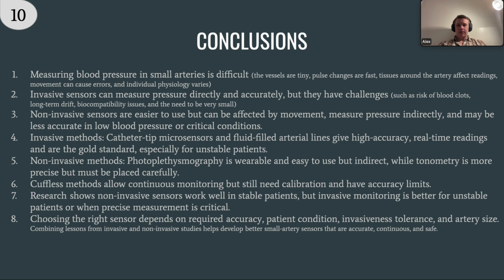Second, invasive sensors can measure pressure directly and accurately, but they have challenges as well, such as the risk of blood clots and infections, long-term drift, biocompatibility issues, and the need to be very small. 3. Non-invasive sensors are easier to use but can be affected by movement, measure pressure indirectly, and may be less accurate in low blood pressure or critical conditions. 4. Invasive methods. Catheter tip microsensors and fluid-filled arterial lines give high accuracy, real-time readings, and are the gold standard, especially for unstable patients, like we saw in the study.